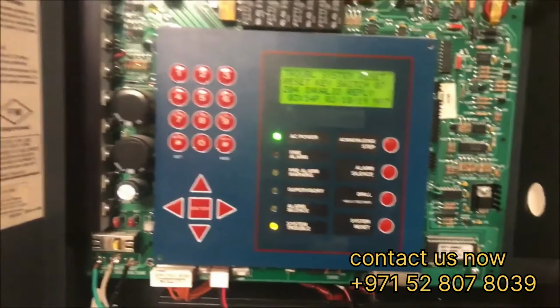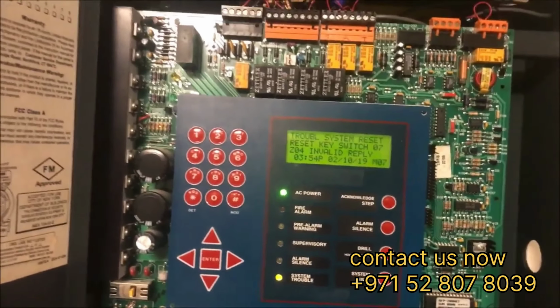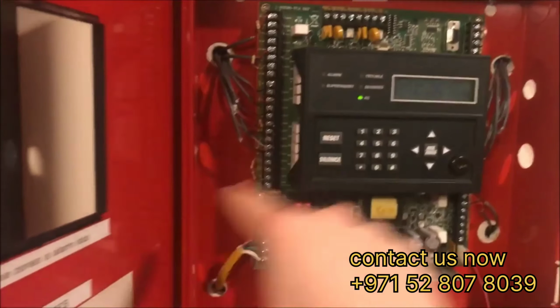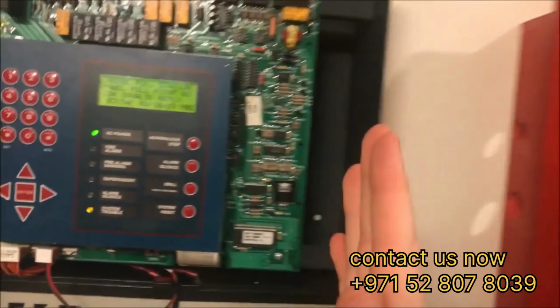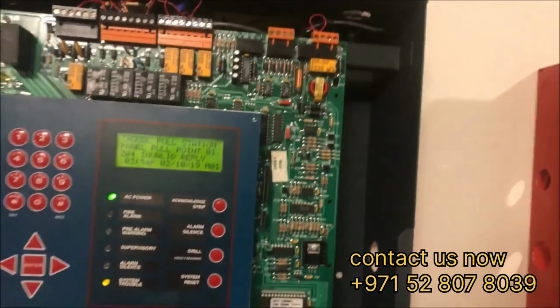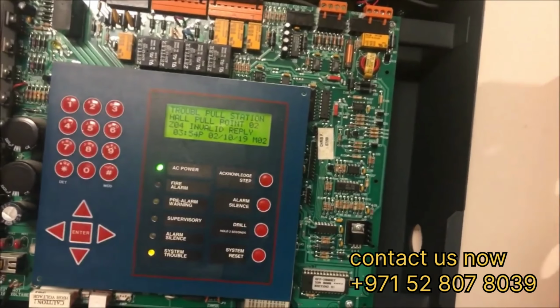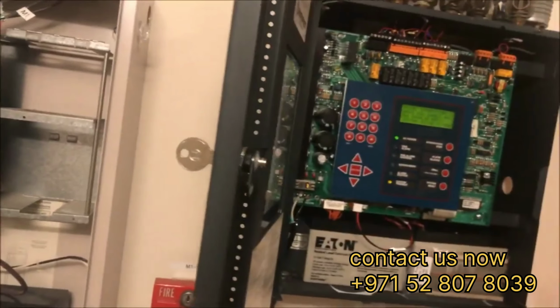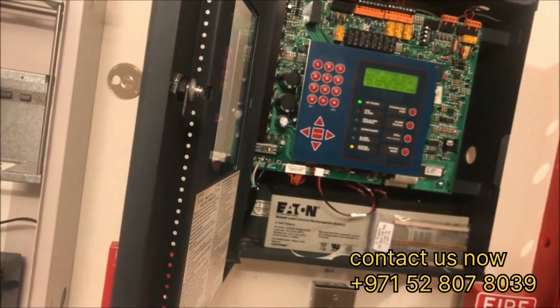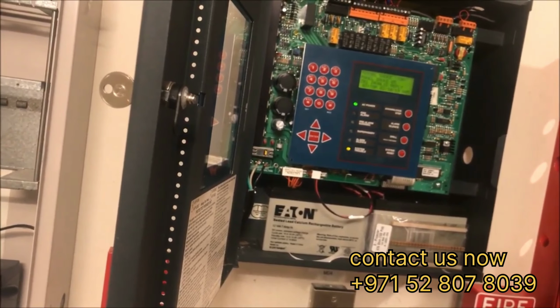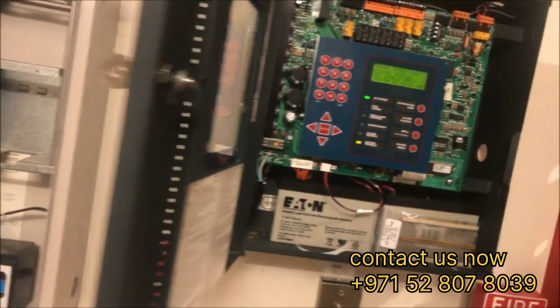And with supervision, because this doesn't have resistors, this means you can T-tap off wires. This one you have to daisy chain through each device to get supervision. This one you can branch and T-tap off the wires because you don't need that end-of-line supervision. You just need the modules to be able to talk back to the panel. I really think that's it.